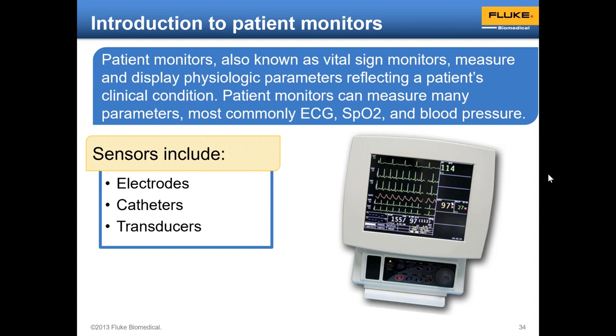So it is true that the patient monitor includes electrodes and catheters and transducers that connect to the patient, some of which are continuously conductive all the way from the patient monitor to where they touch the patient, and others of them that are not continuously conductive and still provide information, like cuff blood pressure, NIBP, for example. There's no electrical connection there, so for electrical safety, we don't care.